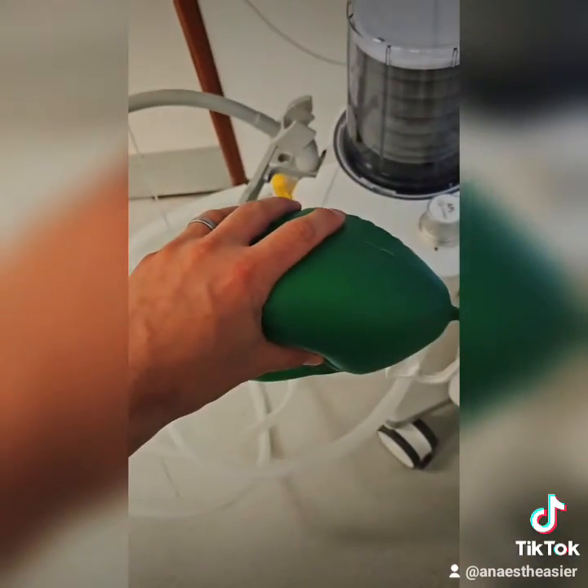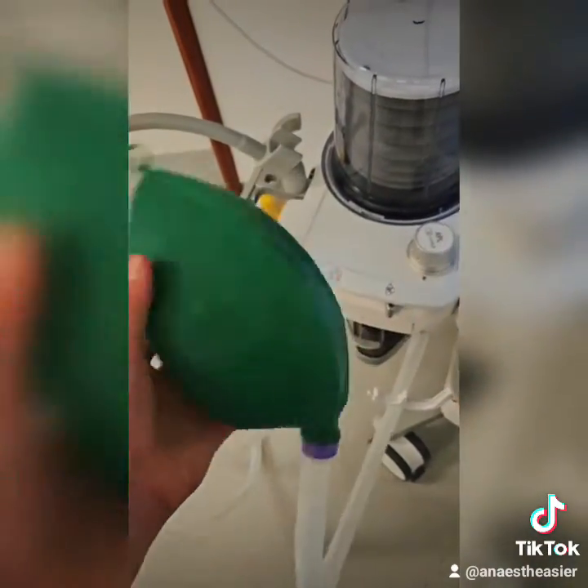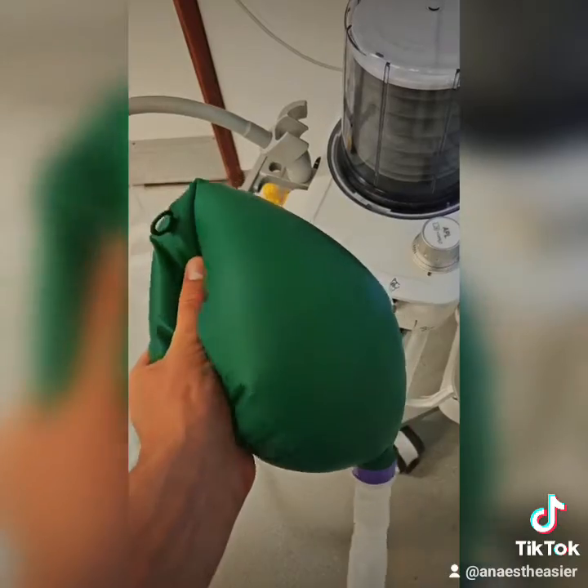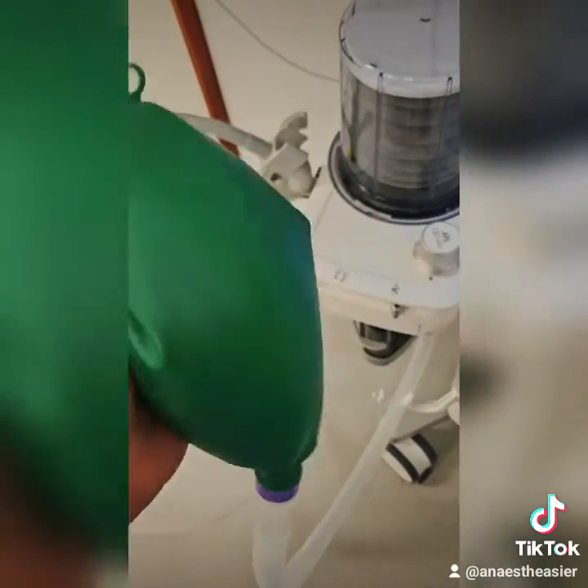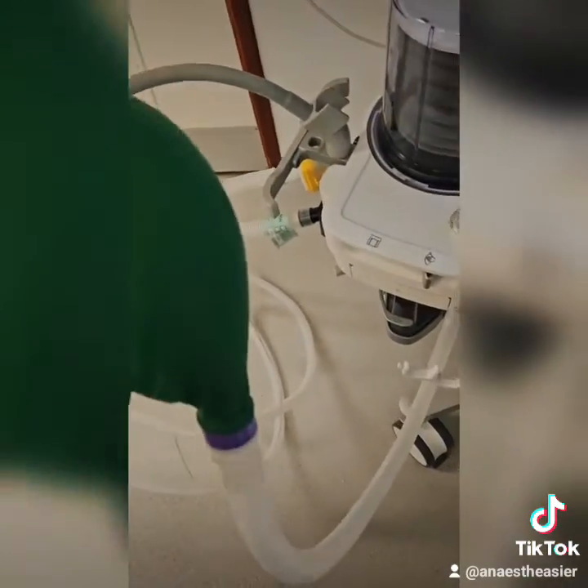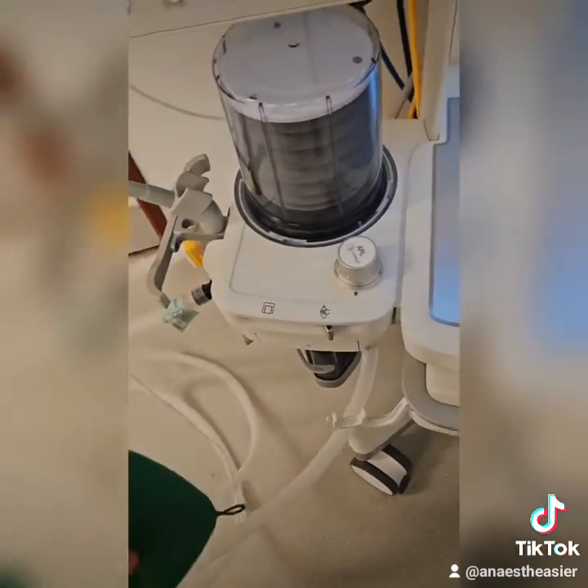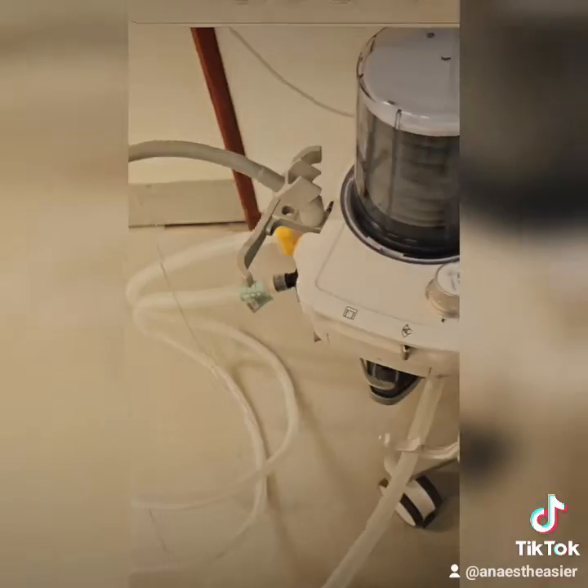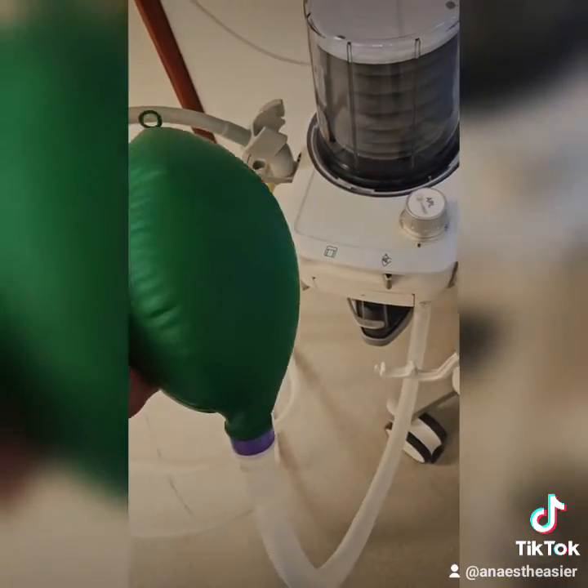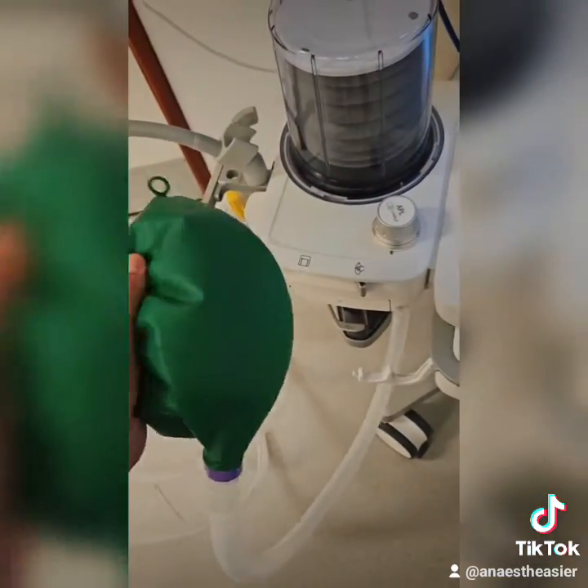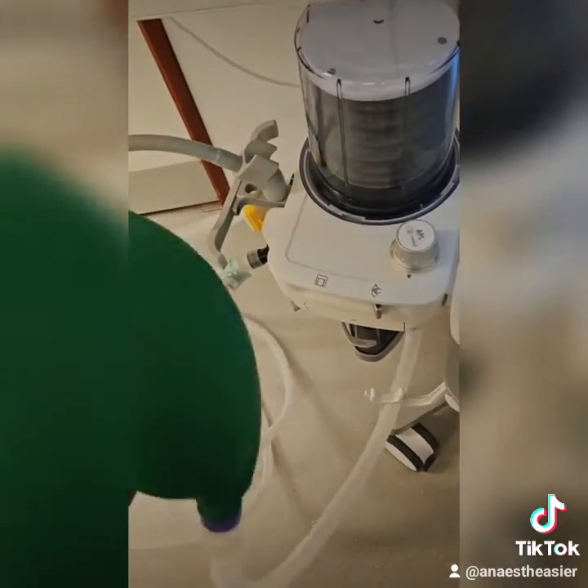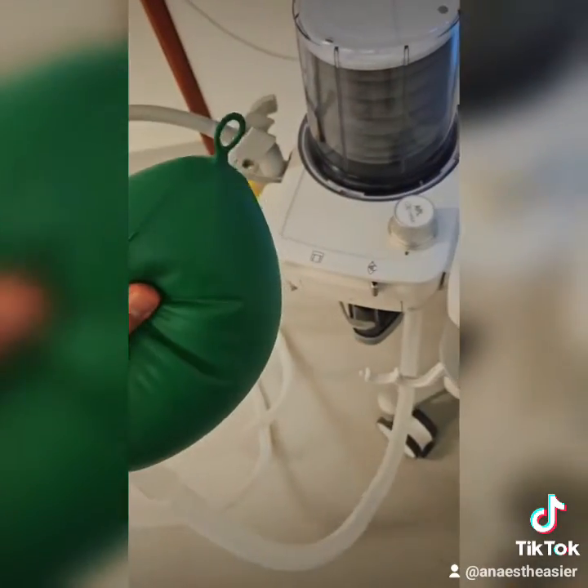Second thing is it allows you to manually ventilate the patient. That's a 2-litre bag, so you can squeeze that and that will push air through the breathing circuit, and it means you can support the patient's breathing. So if you don't want to put them on the ventilator because you want them to breathe by themselves but they haven't started breathing effectively yet, you can just give them some breath. Or if you're trying to resuscitate them if they have any problem during the procedure, that's what the bag's for.